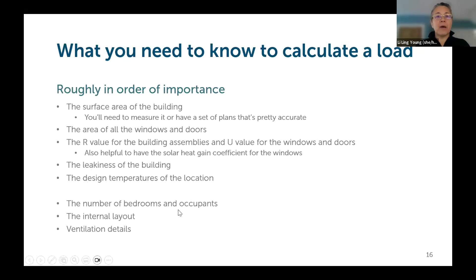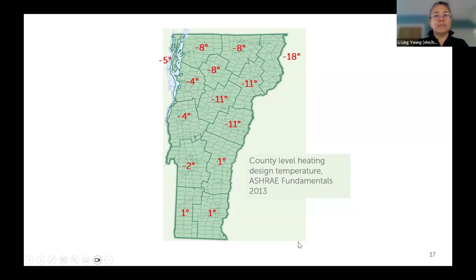I'm going to skip that bottom part and show you this, design temperatures. These are the official design temperatures in Vermont. Do not override this, it's recorded. If you need to come back and find these numbers you can, but look at the counties where you typically work and take on board that there are no places in Vermont where the design temperature is like -26 degrees, even though sure, it has gone to -26 in Vermont. These are design temperatures, they're not supposed to reflect the worst case scenario ever in the history of the planet. Most of Vermont is about -4, -5, -6 degrees. This is the only county up here that's like, whoa, that is super cold up there.